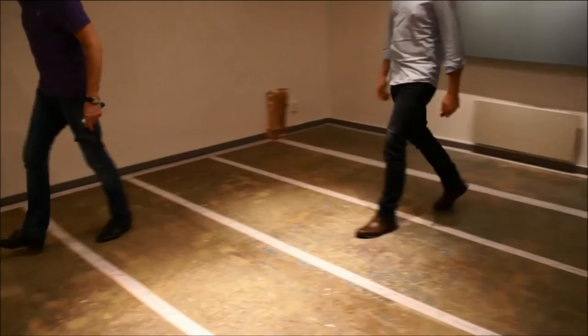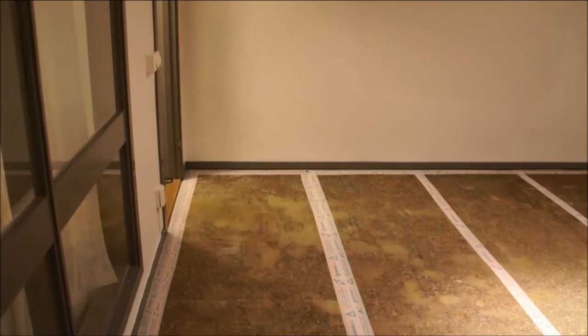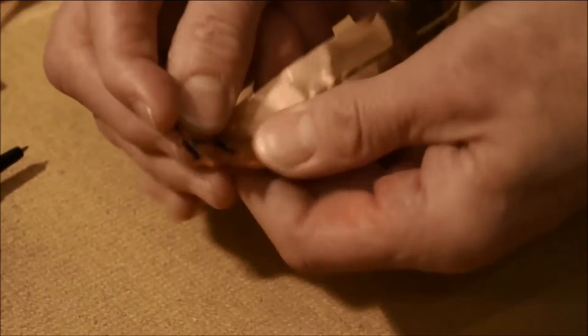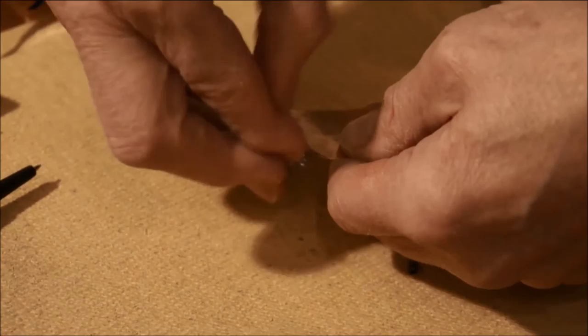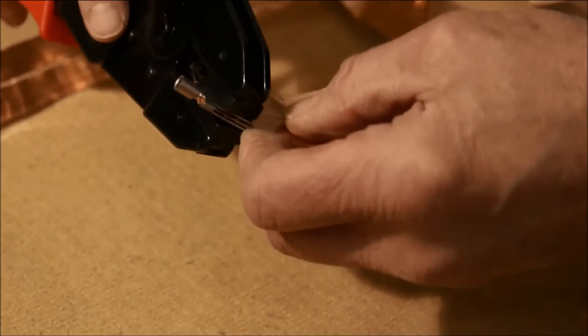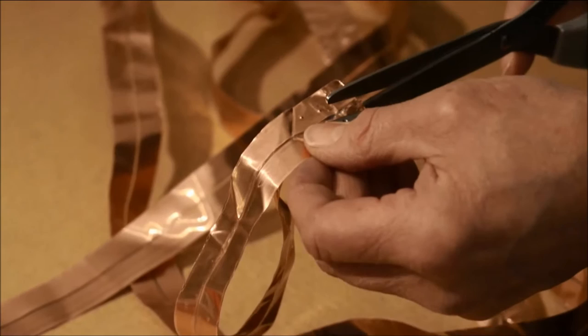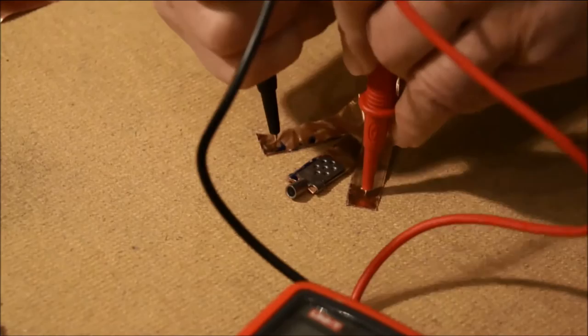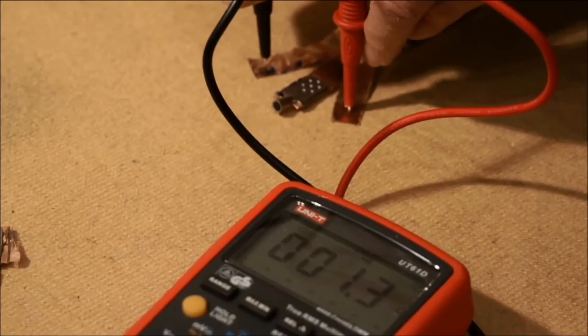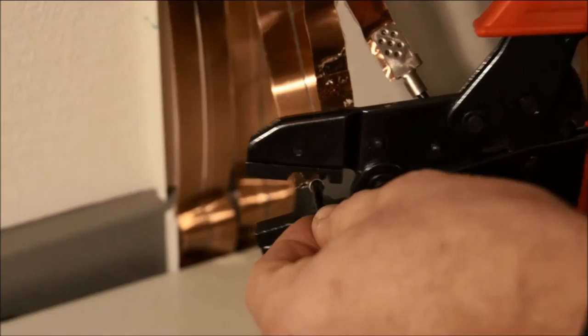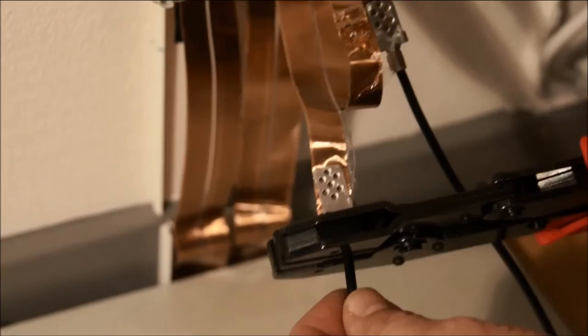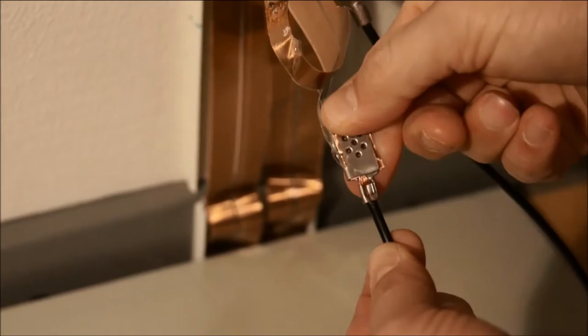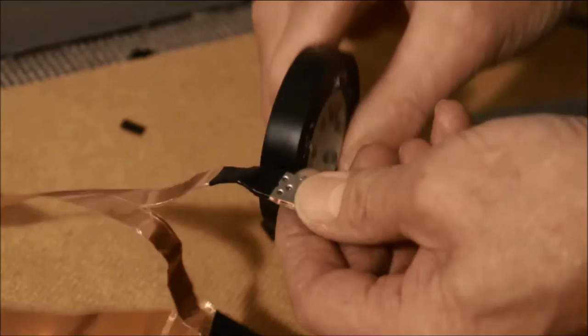The loop cable installation is now completed. Last step is to install the hearing loop amplifier. For this installation we are using twin core cable for a two turn loop, so we serial connect the two cores here by clamping them together, but they can just as well be soldered. Double check for reasonable resistance to verify a good connection between cores. Then connect lead wires to the copper tape. Again we have used clamps but you may also solder. It is important to seal your connection with insulation tape to prevent short circuits.